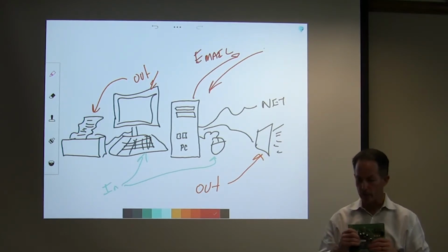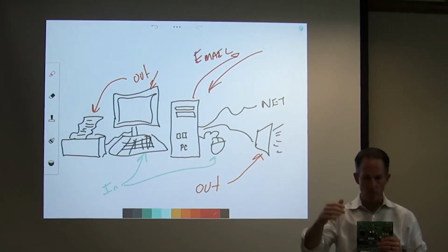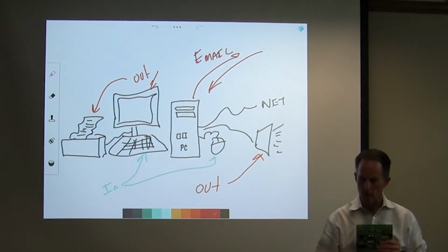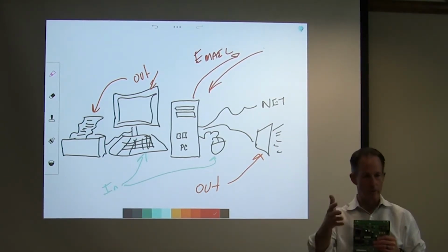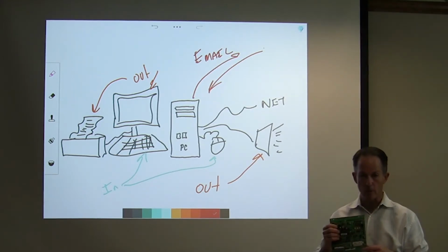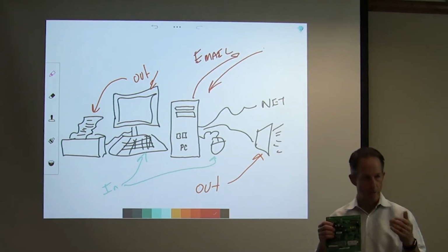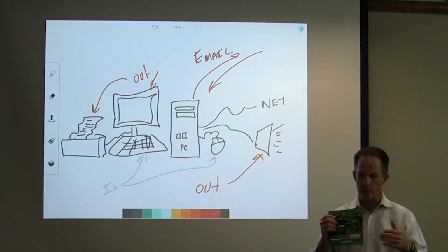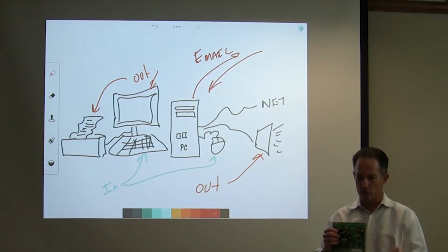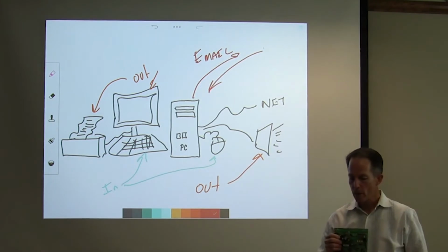When I am tied to a Jace, that will be fluttering. It will basically pull the comm line down to 0, let it go. 0, let it go. And it's using 1s and 0s to send signals down that comm line. It typically will float somewhere in the neighborhood of 2.5 to 3.5 volts when it's communicating. When it stops communicating, it jumps to 5, because all the controllers have a 5 volt, they just pull it up. The head end pulls it down, and that's kind of how they work.